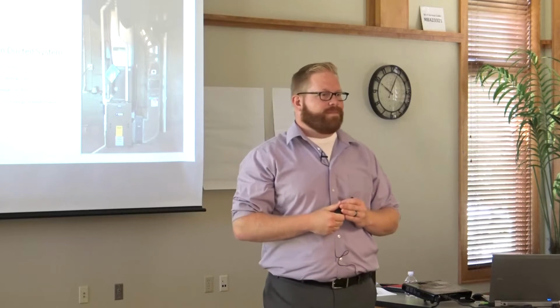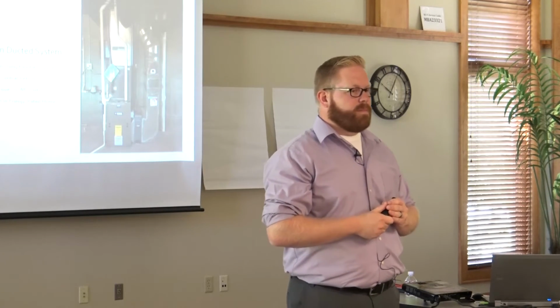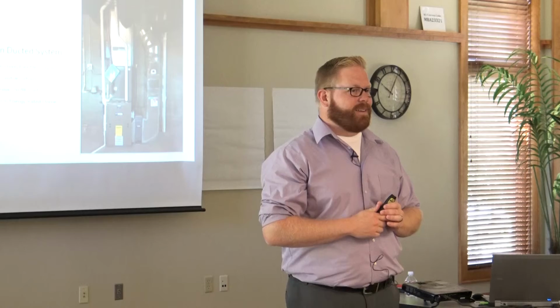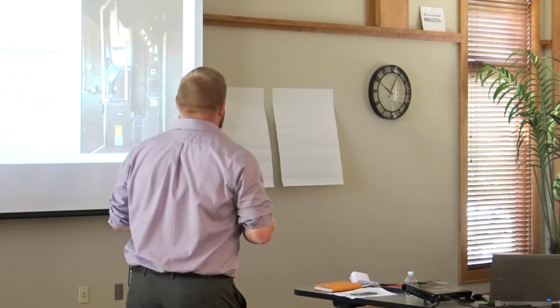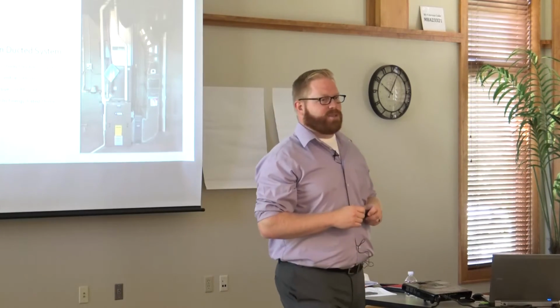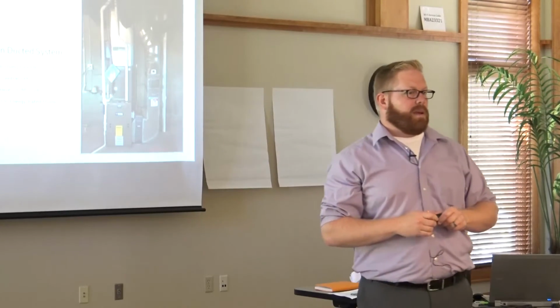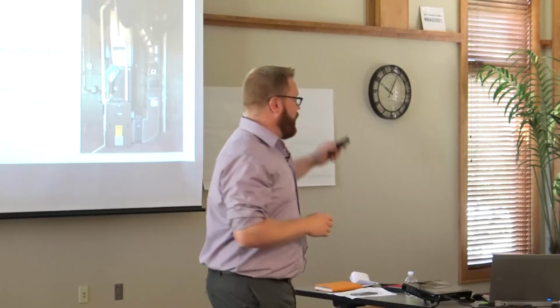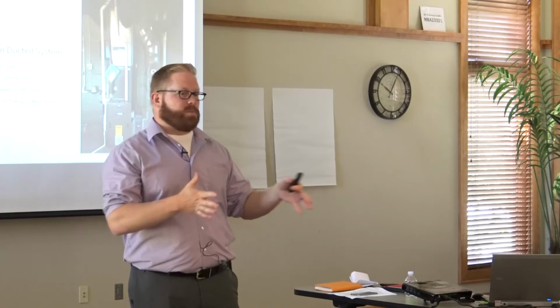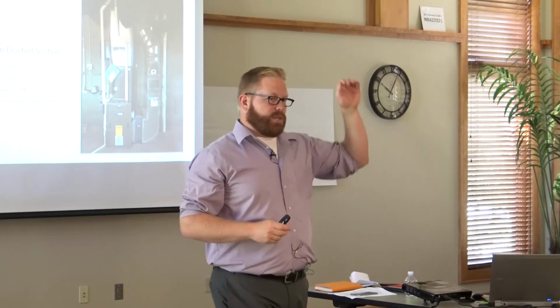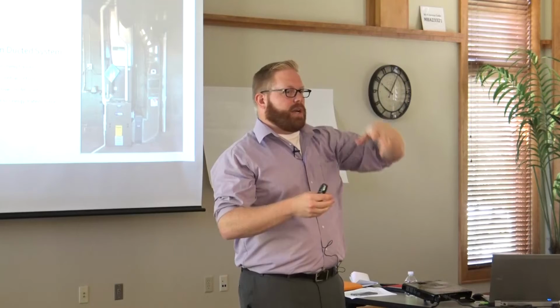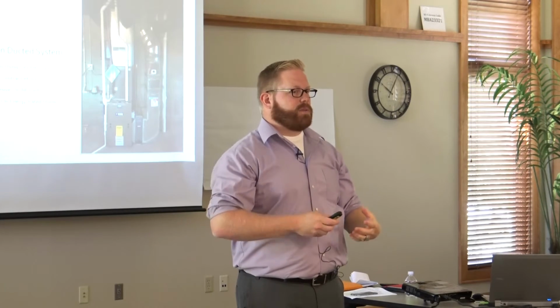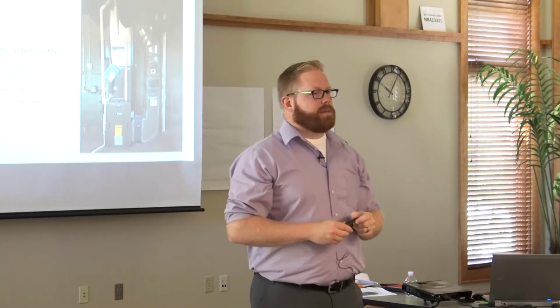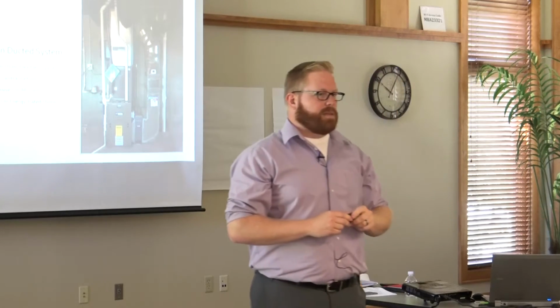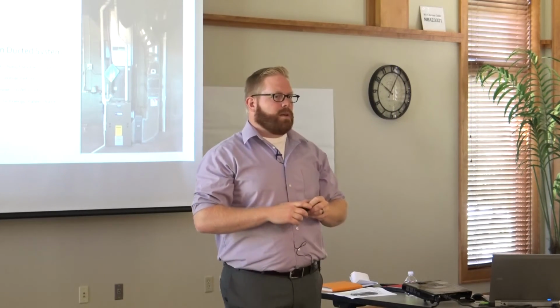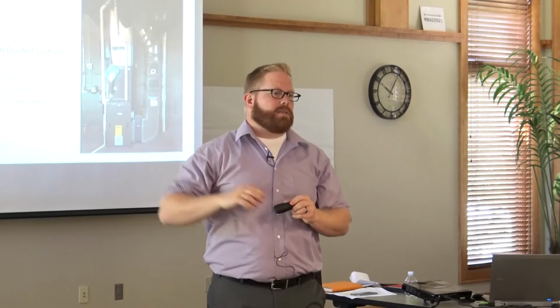Yes, we do - it's the cat watching the hen house, but we do it. How do I know as a builder that it's functioning the way it should? Again, that comes back to the trust of your HVAC contractor. I'd ask the question: if you go down to your system and don't see those specific holes where they can check your delta Ts, check combustion, check airflows, what are they doing? They're guessing, or setting it up based off how it came from the manufacturer, maybe adjusting airflows to match the condensing unit outside.